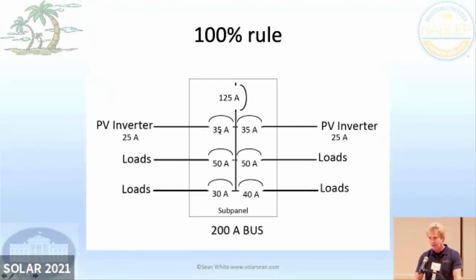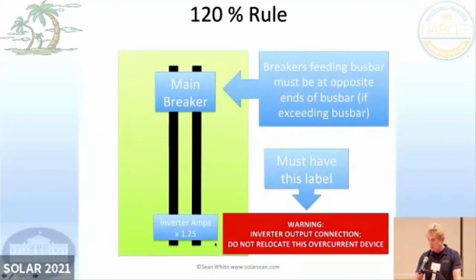And so it's not that hard to relocate things to the opposite end, but you might want to do that. A lot of times it's pretty common to have the bus bar rated for 25 amps more than the main breaker. So you might have a 125 amp bus bar, a 100 amp main breaker, a 225 amp bus bar, and a 200 amp main breaker. Then you could put a 25 amp solar breaker wherever you want. Or if you wanted to go more, you've got to go to the opposite end of the bus bar. And then we're going to see here, if you exceed it by too much, then you can't even do the 120% rule. So let's just look at the 120% rule.